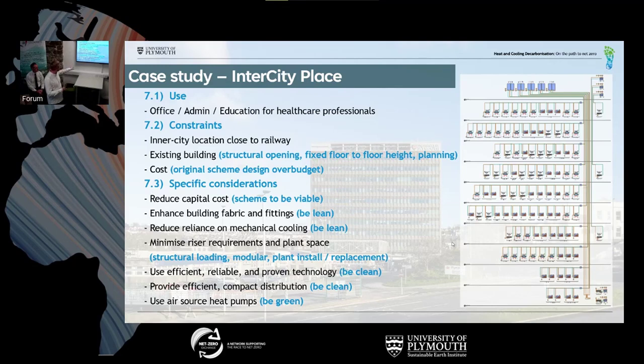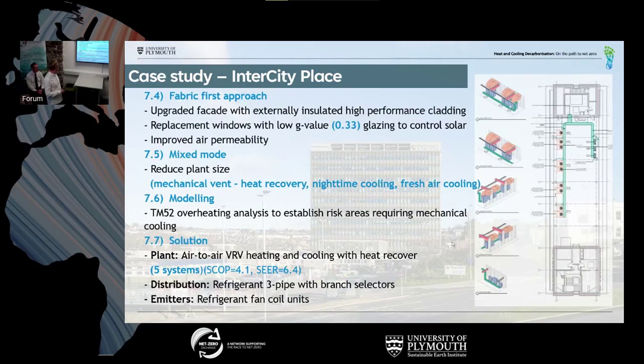I think I'll skip over this since we address it in the next slide. So how did we do that? We upgraded the facade and replaced the windows. We thermally modelled the building using computer software to understand if there was an overheating risk, and we identified that solar control glazing with a G value of 0.33 would really control overheating and reduce any cooling loads on the building.